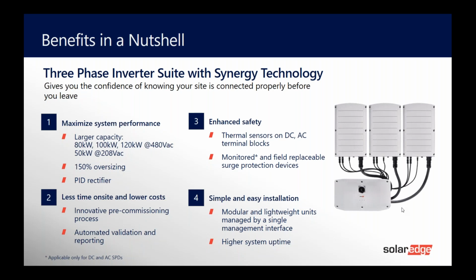Carolyn talked a lot about enhanced safety, and what I want to focus on here is, again, something unique to this inverter, where we actually put thermal sensors on both the DC and the AC terminal blocks in the Synergy Manager. Just to recall, the Synergy Manager is this box here, and these are the Synergy units on top. So we are now monitoring that. If a connection, for whatever reason, is getting loose or not properly torqued, over time the temperature will rise.